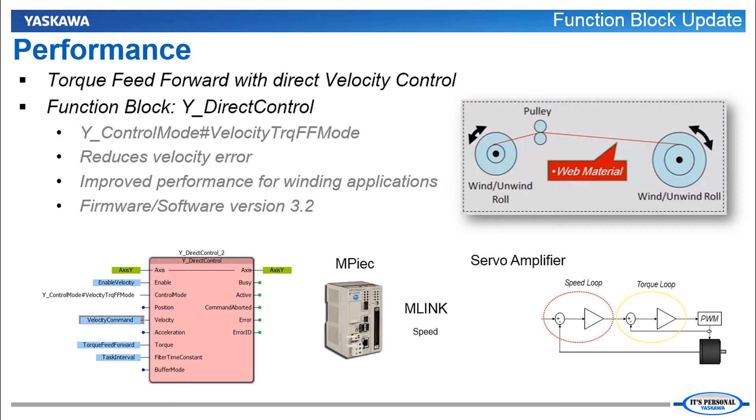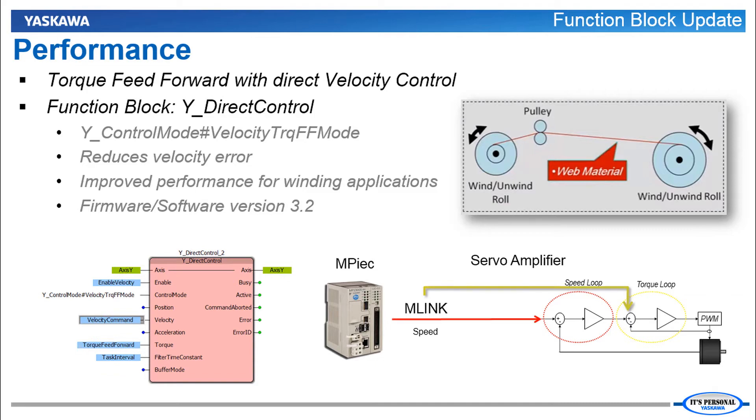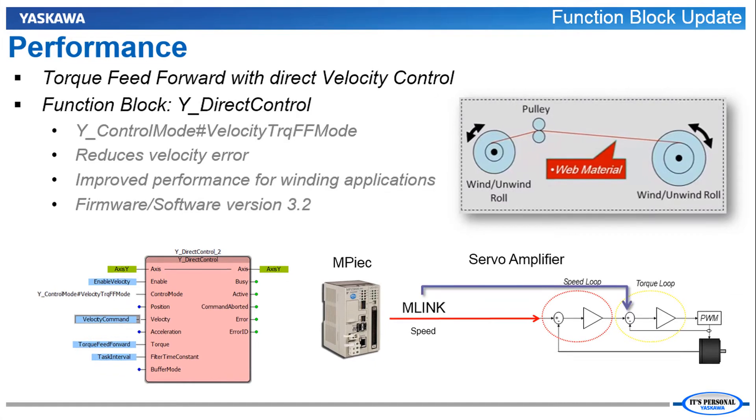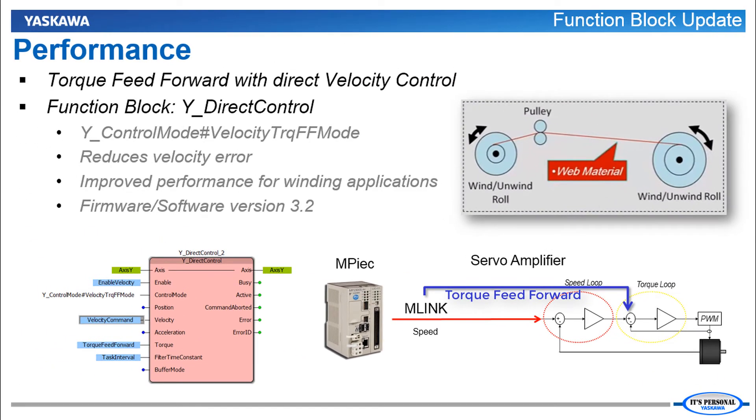Application performance can be improved for winding applications by using Y Direct Control with Torque Feed Forward Control Mode. In this type of application servos drive the wind and unwind rolls. As the roll diameter changes the torque requirements of the motor also change significantly. So the torque feed forward amount can be calculated and gradually changed to predict the torque requirements as that roll diameter changes. This allows the speed loop to operate more effectively. Minimizing the variation in tension and resulting in a high quality product.